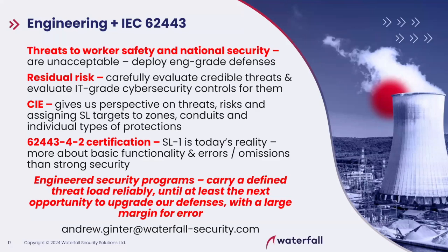It's the operator's job, among other things. The operator has many jobs. One of the jobs is safe operation. It's the job of all of the technology that lets the operators see what's happening. All of the PLCs, all of the HMIs, all the historians, all of the alarm servers are part of the safety program because they show things to the operator who is responsible for safety. Safety instrumented systems are special purpose, whereas a PLC might be used to operate safely and operate reliably and operate efficiently.